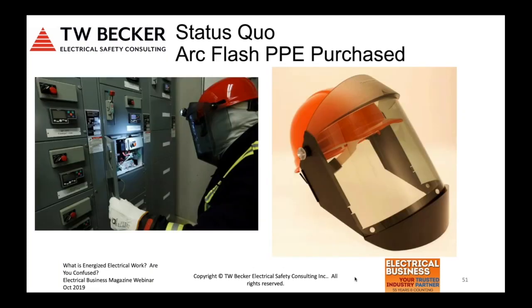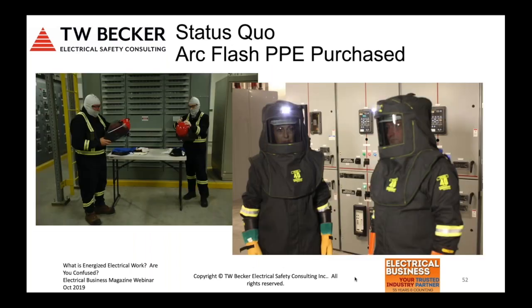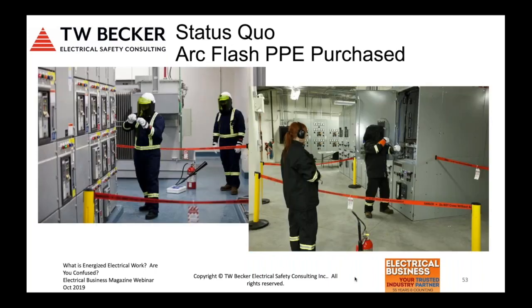So here are some examples of specific PPE that's out there. Now, if you haven't seen this, this is the true color gray PPE that's out there. Again, this is the status quo. This is all available now. Again, LED lamps on the face shields. Again, this is a coverall on the left. It's all sort of status quo now. True color gray lenses on the arc flash suits, LED lamps available for the arc flash suits. Again, some old shields, you can see the green tint on the left.